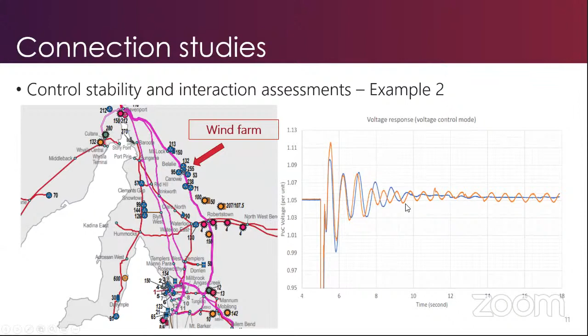Once the fault is cleared, we noted oscillations, as you can see in the graph, the orange line - sustained oscillations. When we carried out an investigation to find the reason, we found that the voltage control gains were too high, resulting in this wind farm fighting itself when controlling voltage. So it was retuned, and you can see the blue trace showing more stable operation.